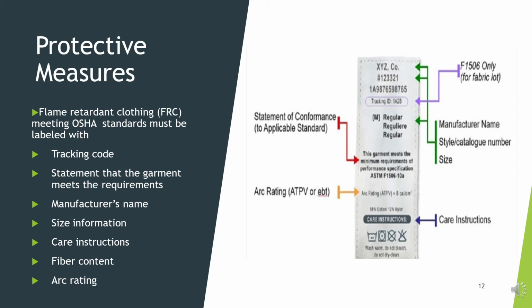OSHA has strict guidelines in their standards for labeling instructions for manufacturers who make FR clothing. It's important that you don't just throw on a pair of coveralls thinking 'oh, they're FR, they're good' — no, they have to meet a specific requirement. Make sure you understand the voltage you're working with and that you have the right coveralls for that. I'll tell you the coveralls we issue are 8 calories, and they're more than enough for the maximum 13.2 kilovolts we're going to be working around.